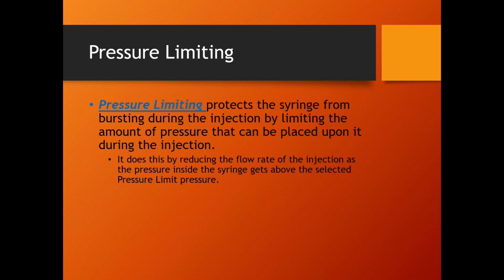Now the reason it does that, let's say we're shooting a flow rate of 5 milliliters per second, and for whatever reason it hit our pressure limit. So the system doesn't stop, but it'll slow down just enough to keep the pressure just below maximum during the actual injection. So we don't exceed 300 psi, we'll just keep it a little bit below 300 psi. Now that might just require us to go from a flow rate of 5 milliliters per second to 4.8, all right? We'll still get an image. The image will still work, all right?